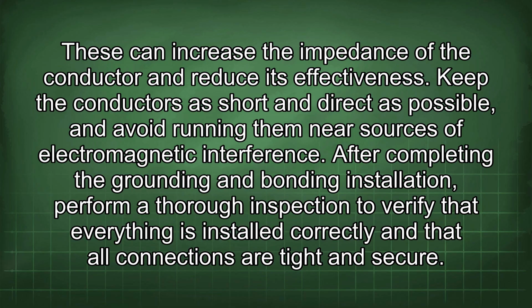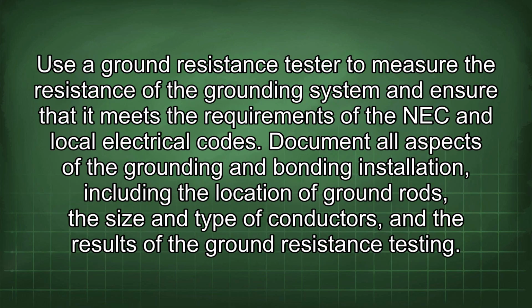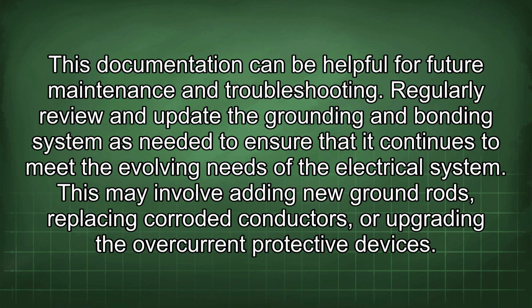After completing the grounding and bonding installation, perform a thorough inspection to verify that everything is installed correctly and that all connections are tight and secure. Use a ground resistance tester to measure the resistance of the grounding system and ensure that it meets the requirements of the NEC and local electrical codes. Document all aspects of the grounding and bonding installation, including the location of ground rods, the size and type of conductors, and the results of the ground resistance testing. This documentation can be helpful for future maintenance and troubleshooting.